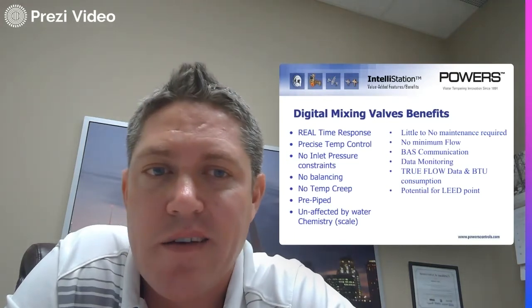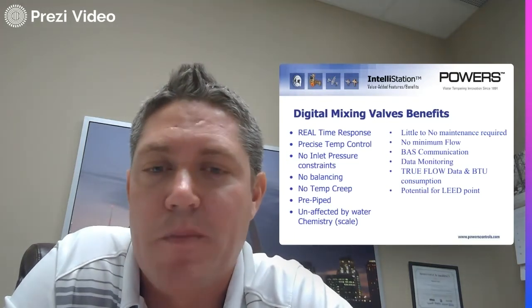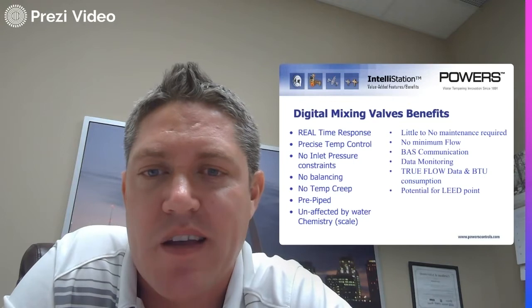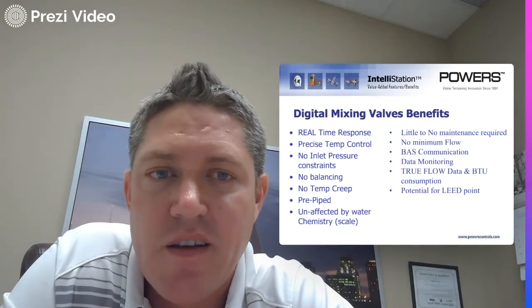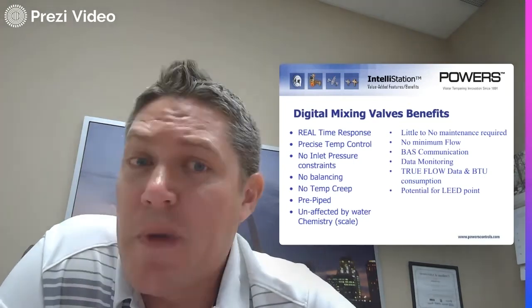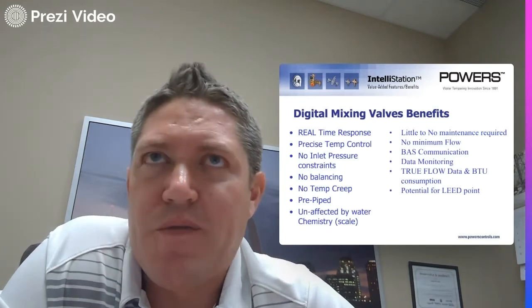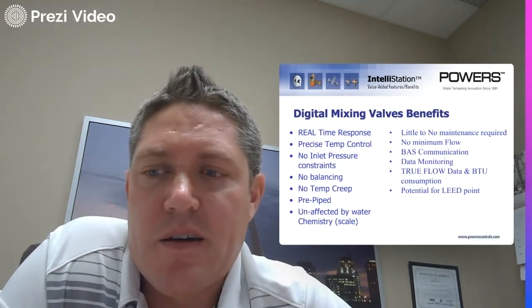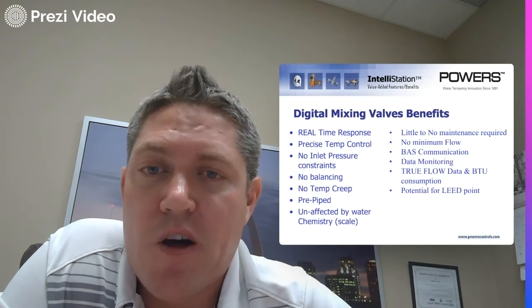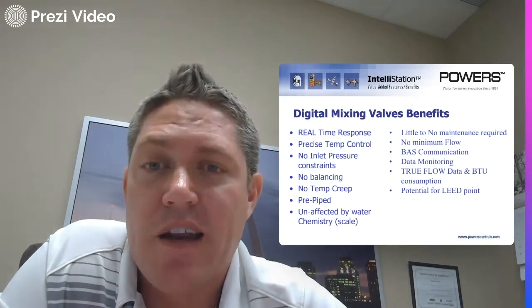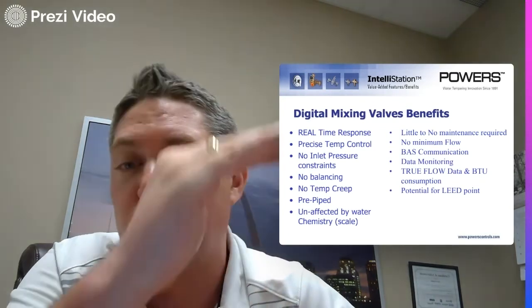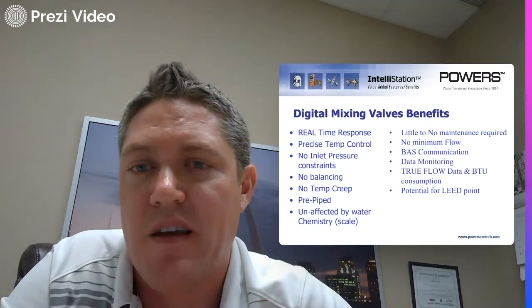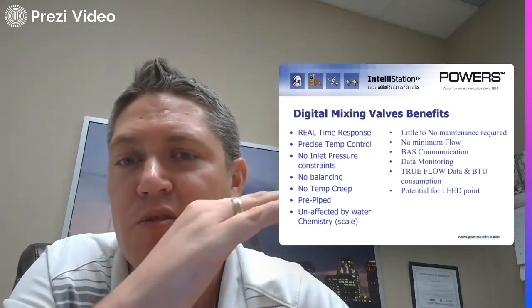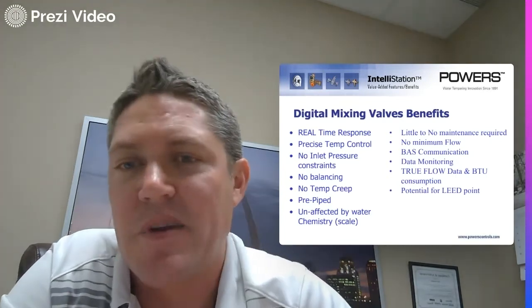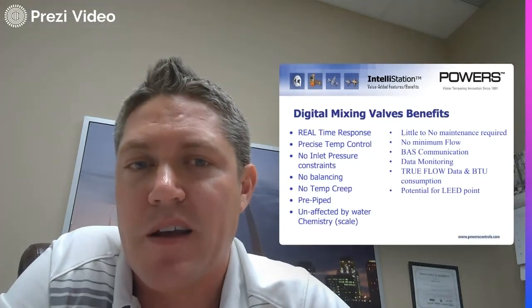Time to set it is dramatically decreased. I mean, once you've got it piped up, you can set that valve in 2 minutes. No minimum flow. I mean, there's a 0.5 gallon per minute minimum flow on digital mixing valves, but it eliminates the need to have a high-low 2-valve system, because even your smallest mixing valve on a high-low thermostatic system is going to be down around 0.5 gallons per minute.